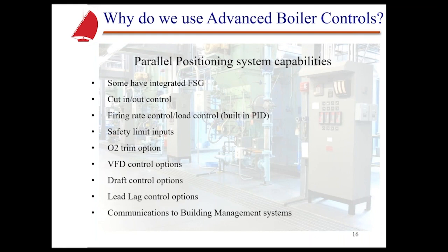You can also have cut in and cut out control. So with a parallel positioning system that has the ability to do the modulation and actually be the flame safeguard, we can control when the burner comes on and when it's turned off if the load is satisfied. Also, the firing rate control. Many parallel positioning systems will become the load control because they will have a built-in PID controller.